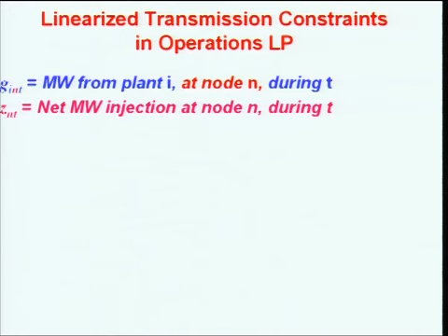So to solve this, I need another decision variable, which I'll call Z, the net megawatt injection at a node. If you have more generation than demand, Z is positive. If you have more demand than generation, Z is negative. That's what goes into the network and then has to be distributed in your load flow.